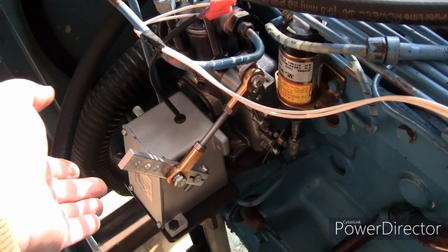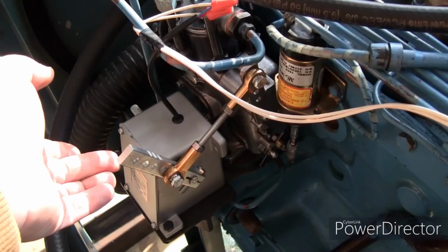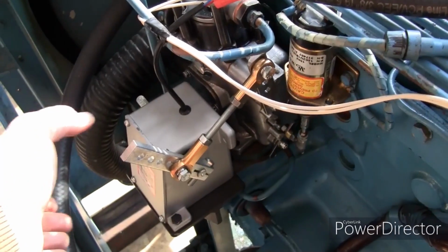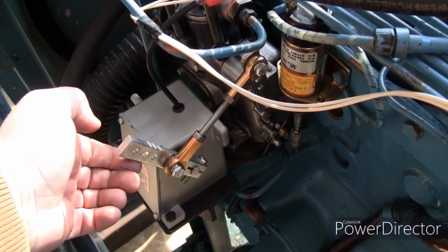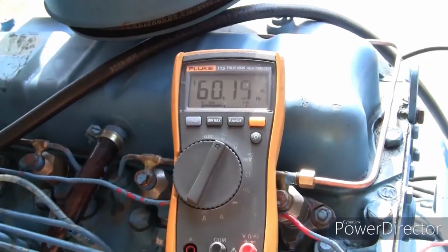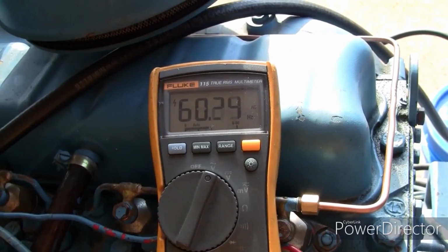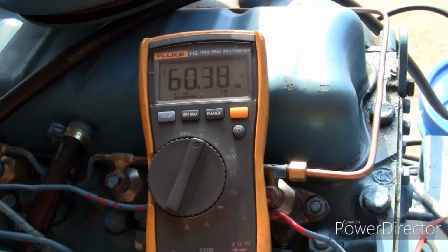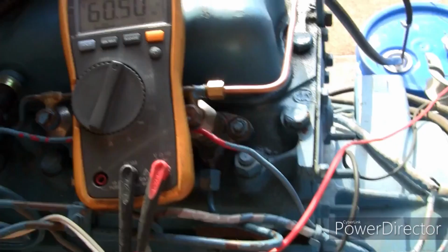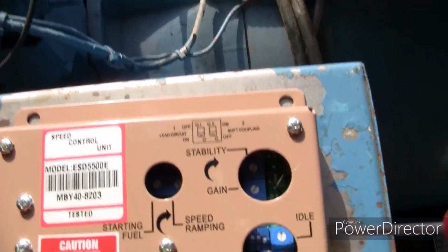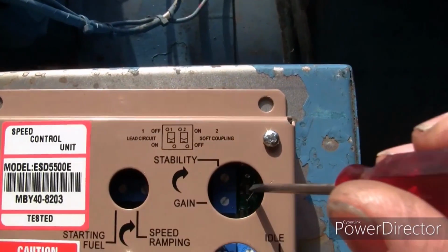Now that we're at about 60 hertz, you can see I can bump the throttle and it does move back to a set point, but can you see when I flick there, it's kind of bouncy? It doesn't really have a lot of ambition to move back where it's supposed to. But we're at about 60.5 hertz. So I'm going to start turning the gain adjustment up a little bit here.